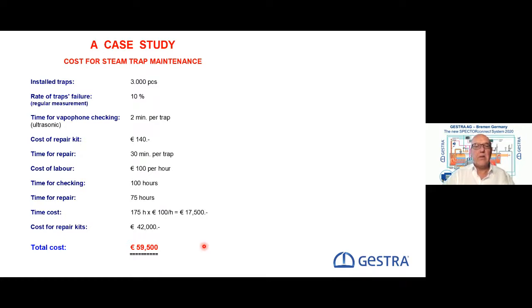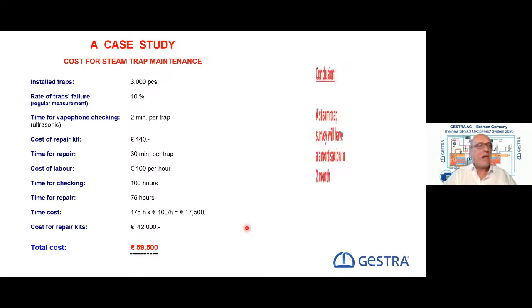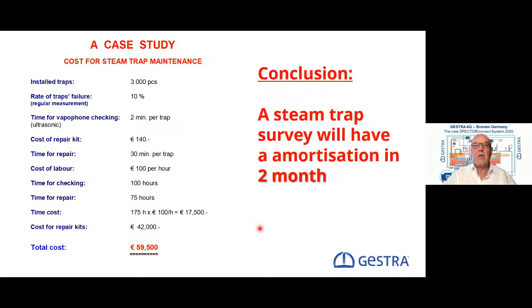And this is cost of ownership, I would say, that we also should not forget. If we do this, we have to make an annual check of the steam traps by an ultrasonic device with the help of the GESTRA opcos around the world. And we can say at the end, this steam trap survey will have an amortization in around about 2 months if you order this check of the steam traps.